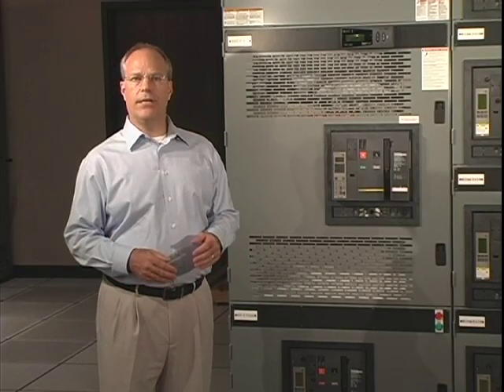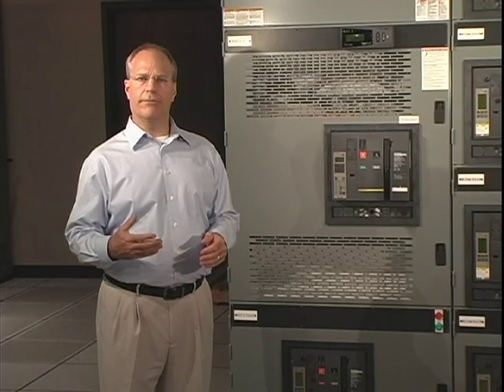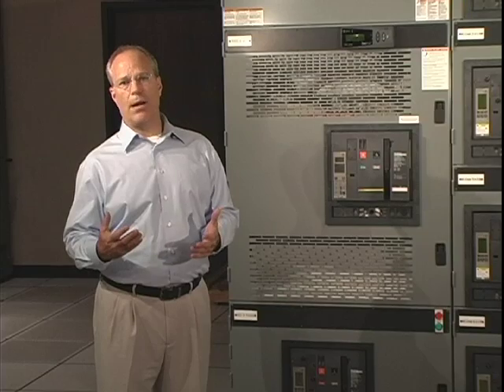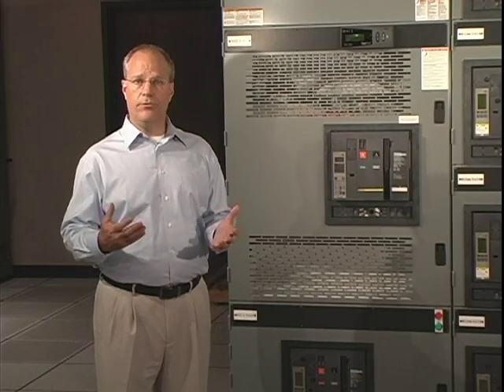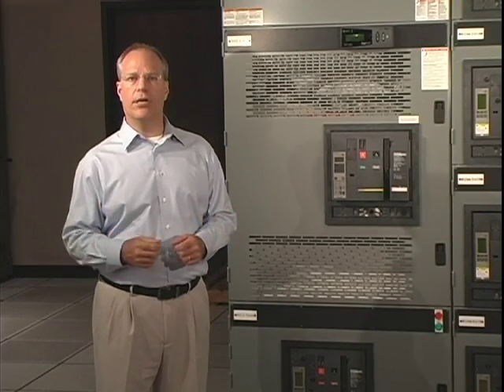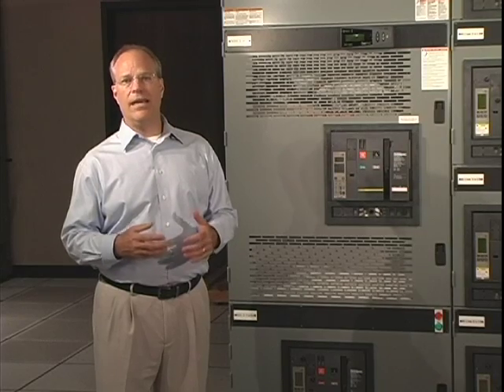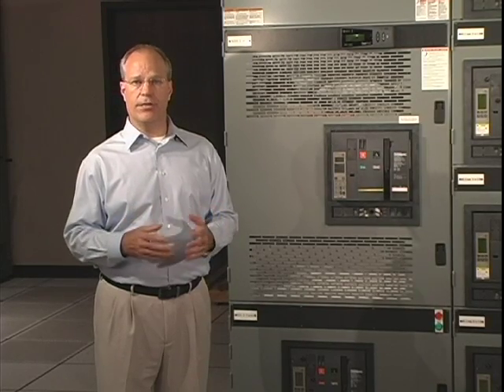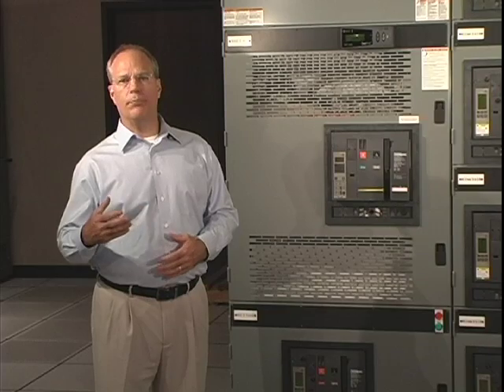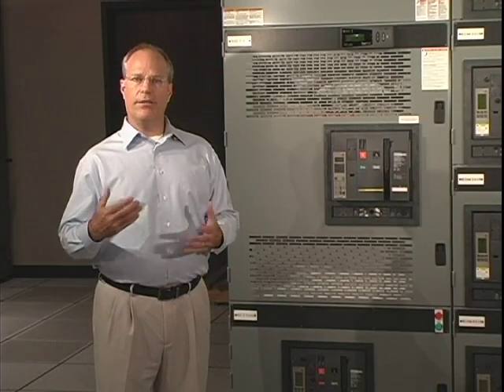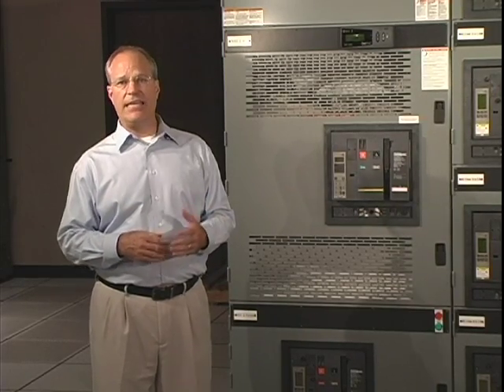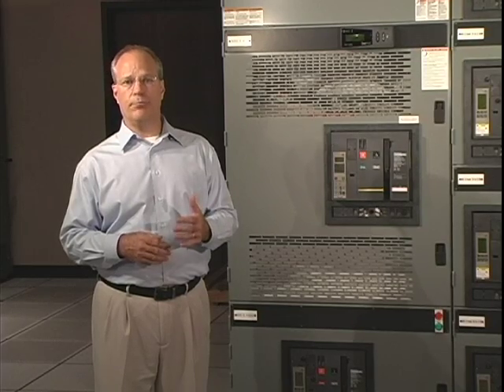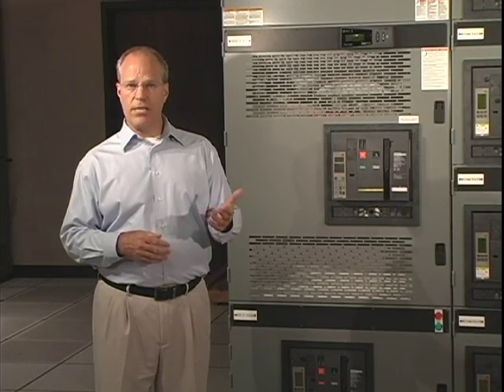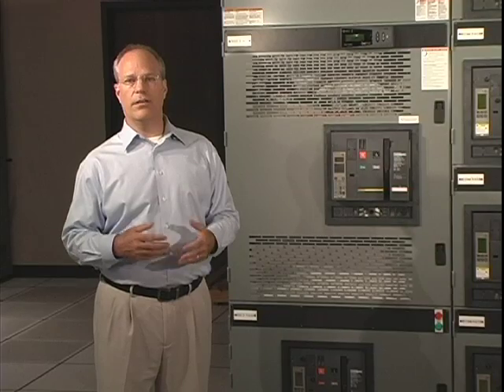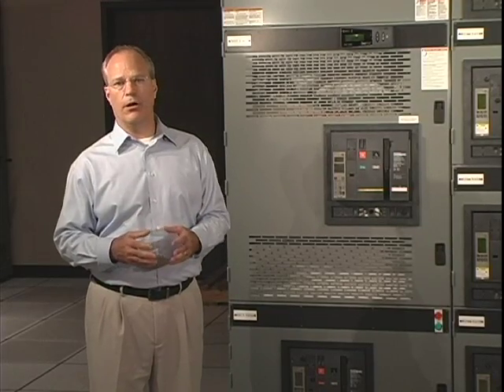Schneider Electric understands the importance of continuity of service in our customers' critical power applications. We're committed to providing transparent communications to help our customers understand and mitigate risks that may affect their system. It has been reported by some of our customers about unexpected trip events involving the STR model electronic trip units. The following three conditions must exist for the unexpected trip events to potentially occur.